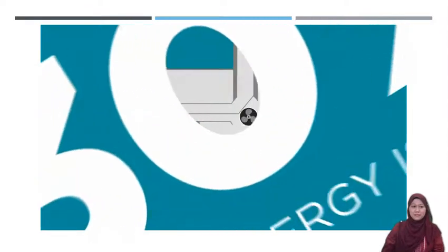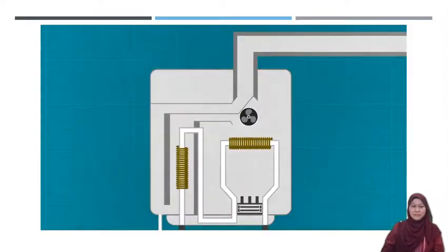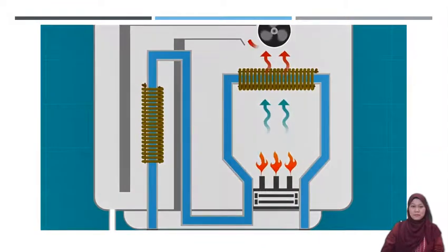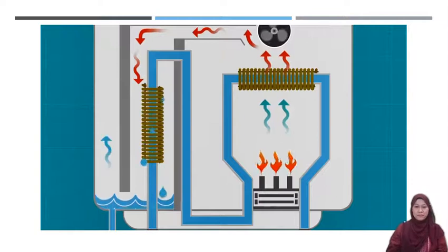Replacing the conventional boiler with a condensing boiler can add efficiency to any hydronic system. Condensing boilers have two heat exchangers. The first, like the non-condensing boiler, is heated by the gas burner. The second captures the excess exhaust gas heat from the primary exchanger. The heat that is normally exhausted is waste. The high-temperature water vapor in the exhaust gas condenses into liquid water, releasing a large amount of heat that is transferred to the cool water as it first enters through the secondary heat exchanger.